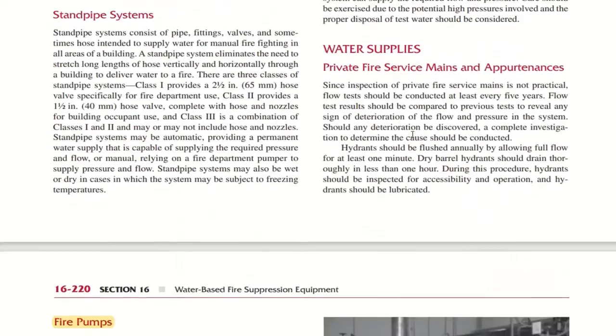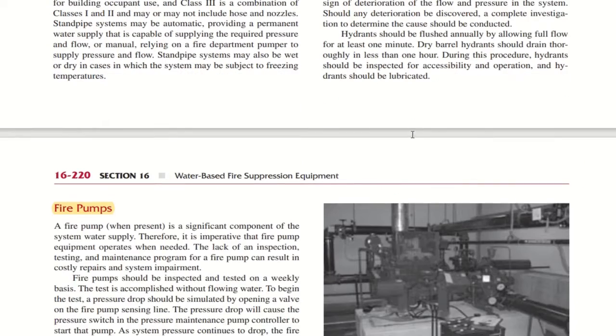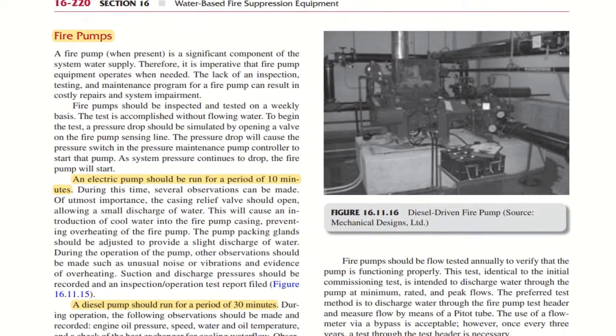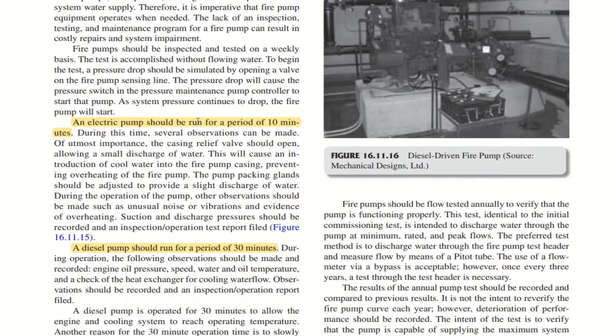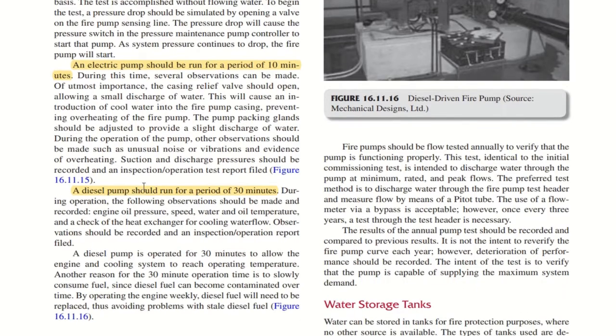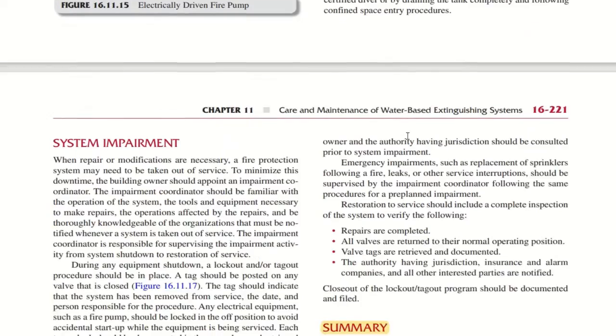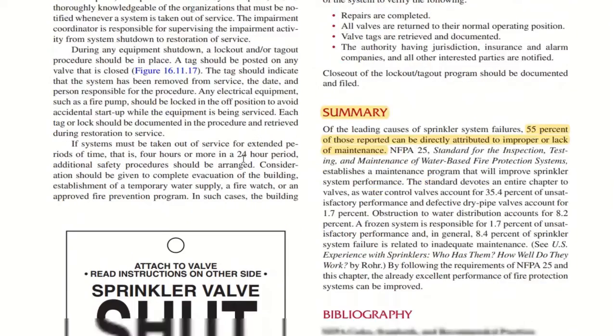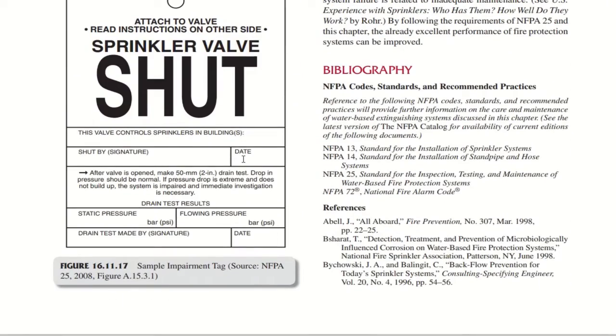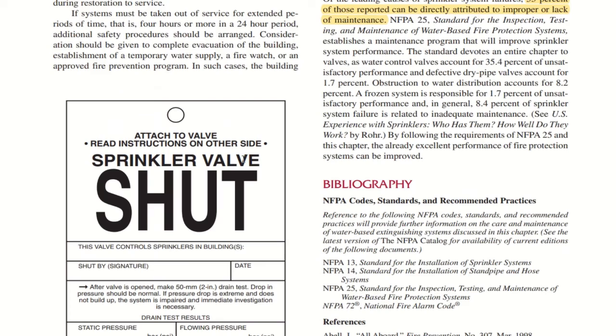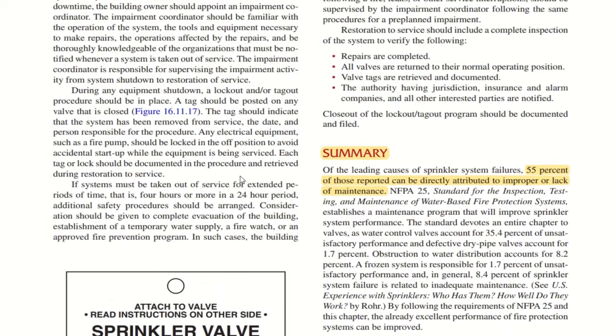And you have several types of systems. Fire pumps are also covered here, since this chapter is covering maintenance. So this is covering the equipment as well, especially fire pumps. An electric fire pump should be run for a period of 10 minutes. A diesel pump should run for a period of 30 minutes. Water storage tanks are also shown here. So this is a sample impairment tag also, you can use this in your installation as well.